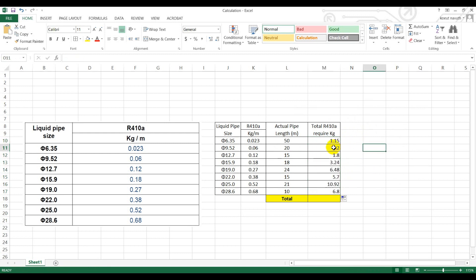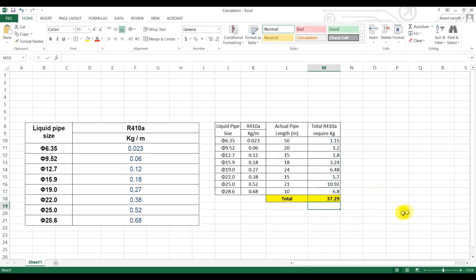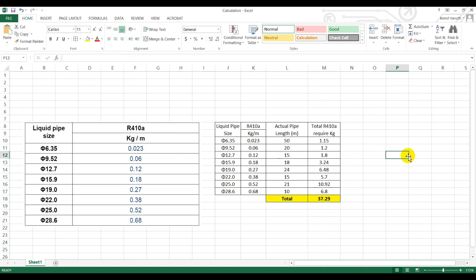And then we go to another side. This is for 9.52, this is for 12.7, and following up until this maximum size of 28.6. Now the total refrigerant requirement is, in this example system, you have to add 37.29 kg to the system.